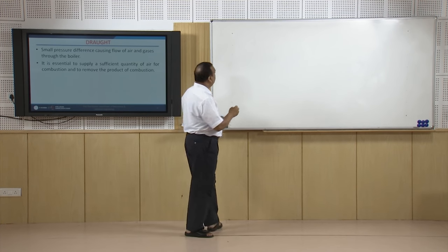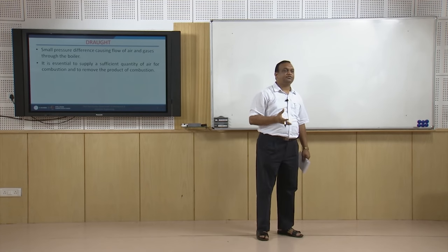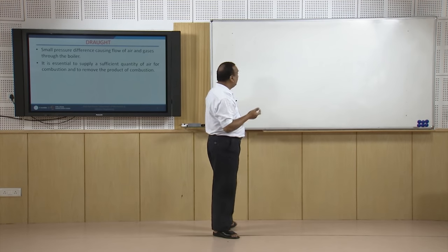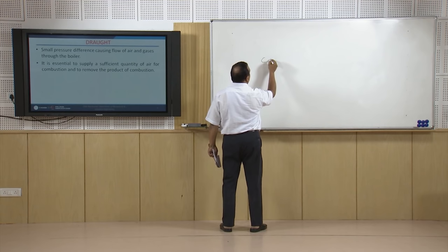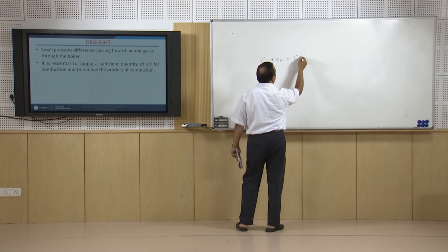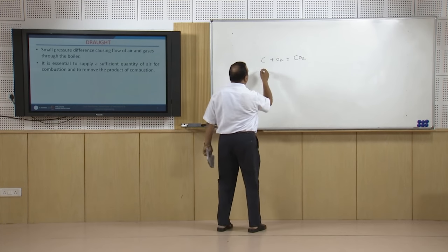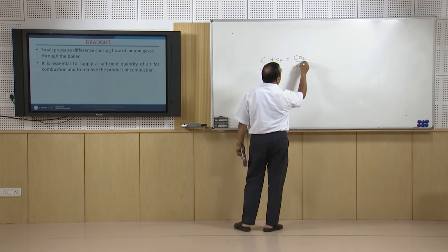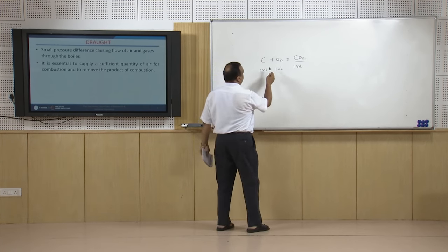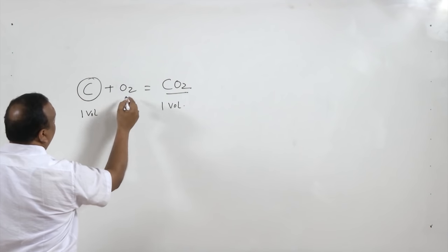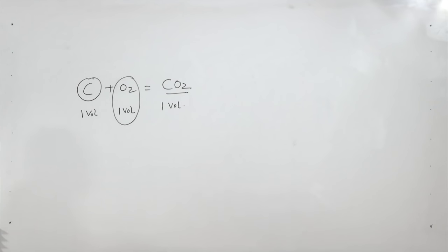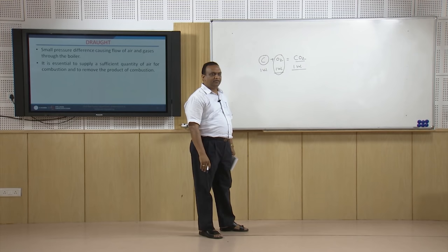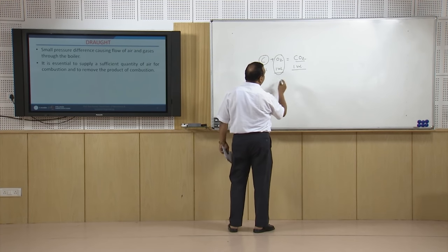Before calculations, let us understand the theory of combustion. In fuel, carbon constitutes approximately 78–85%. Carbon burns with oxygen to form CO₂: one volume of carbon plus one volume of oxygen gives one volume of CO₂. This means the volume of air is approximately equal to the volume of flue gases, since nitrogen does not participate in combustion. This equality of volumes holds when both are compared at the same temperature.